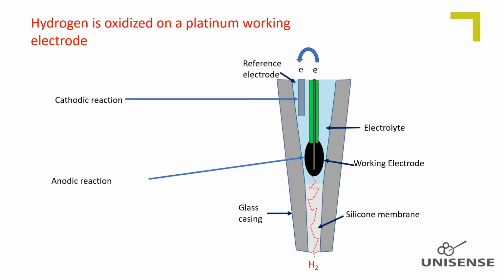Details and general theory about Unisense amperometric microsensors are covered in the lecture about Unisense amperometric microsensors, but I will here briefly describe the chip design and working principle for the hydrogen microsensors. The outer tapered glass casing is equipped with a silicone membrane. The function of the membrane is to make a barrier between the electrochemistry inside the microsensor and the sample. The membrane is permeable to hydrogen. If hydrogen is present, it diffuses through the membrane to the working electrode. The working electrode surface is a positively polarized platinum electrode, which catalyzes oxidation of hydrogen. The electrons are delivered to the reference electrode, where a dissolved substance in the electrolyte is reduced.